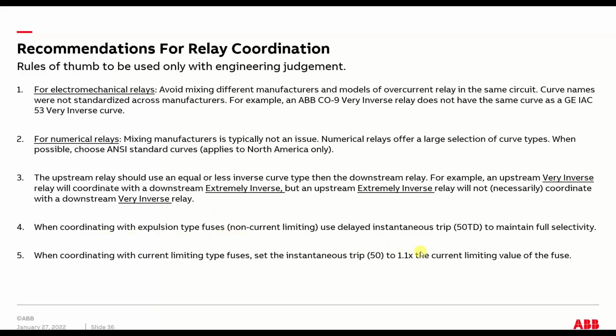Here's a couple little tips on coordinating with different types of fuses. If it's an expulsion fuse, you usually want to use a delayed instantaneous. If it's a current limiting fuse, you can use full instantaneous protection, no delay. A rule of thumb is you set that to about 110% of the current limiting value of the fuse. That gives you enough clearance time.